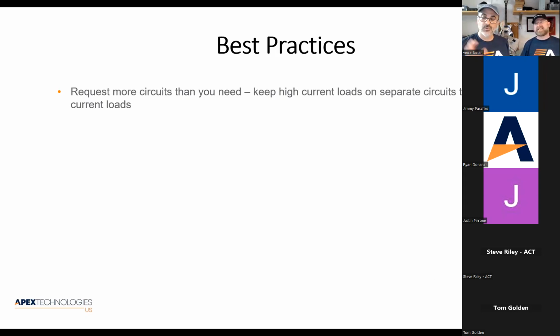So, the one thing that you do a great job is you do a power audit, right? You know how much power you need. Request more than you need, right? Ask for more. If they give you less, at least you get what you want, right? You probably already know this: keep those high current loads on separate circuits, right? Keep the lower current loads on one. We don't want the high current loads disturbing what's going on on those low current sides.